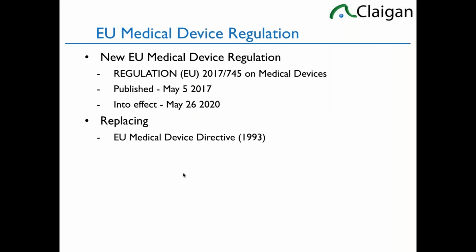So on to the EU medical device regulation. The new MDR, Regulation 2017-745 medical devices, merges the old Medical Device Directive and the Implantables Directive into one. IVD still has its own regulation. Even though it says April 5th on the actual text, it was published on May 5th, 2017, and it goes into effect more or less May 26, 2020. We'll talk about the "more or less" part in a moment. So we're looking at a May 2020 more or less deadline, but we'll explain some of the details around that.